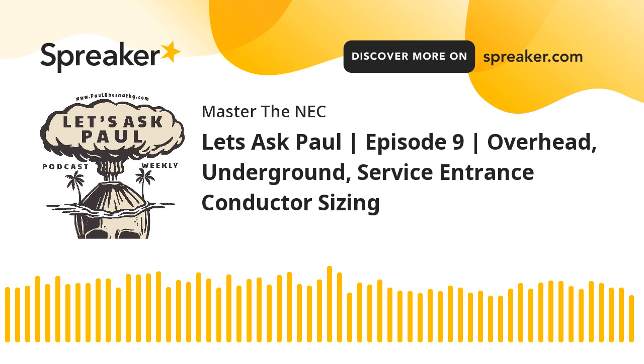All right, so it goes on to say, now let's size. What do we do for sizing that grounded conductor? It says, under 230.23(C), and again, we're talking overhead service conductors, the grounded conductor shall not be less than the minimum size as required by 250.24(C). Okay, so 250.24(C) is talking about the grounded conductor brought to service equipment. Now, we're not talking about a need for a neutral downstream of your service equipment. That is purely optional depending on what your loads are. Maybe you have loads that don't need a neutral. Maybe you have a panel that's designed to handle this situation and there are no neutral loads in it. It's only handling phase-to-phase types of loads. There are allowances downstream, but when it comes to the service, you have to bring a grounded conductor to the service.